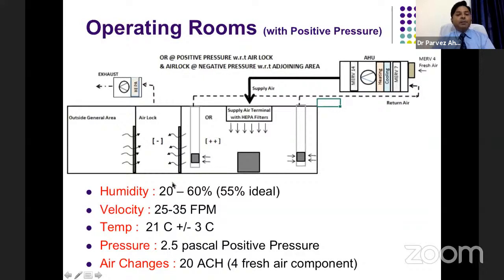Humidity should be maintained at 20 to 60%. NABH recommends that 55% humidity should be maintained, which is ideal inside the operation theater. Velocity should be maintained at 25 to 35 feet per minute. Temperature should be 21 degrees Celsius plus or minus 3 degrees Celsius, although in joint replacement surgery operation theaters, temperature can be maintained a little lower.